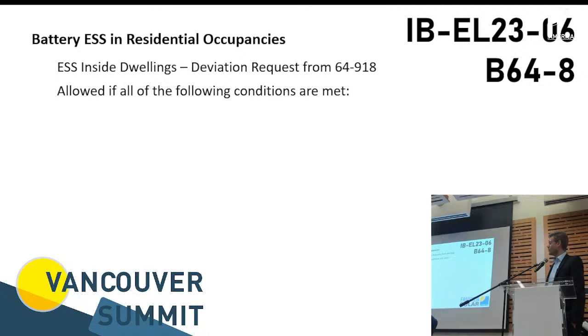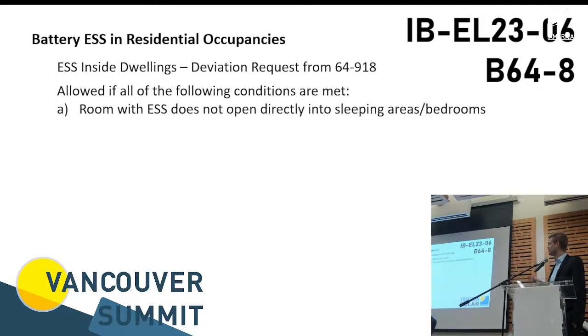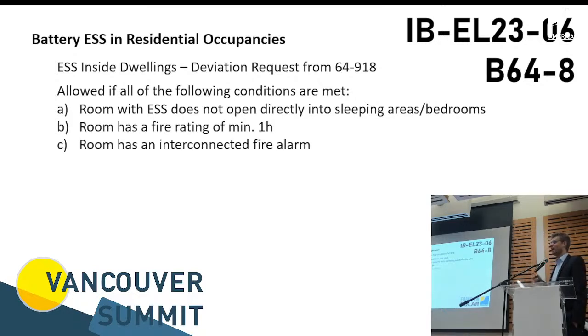When we want to install it in a dwelling, there are certain deviation request options, either in Bulletin 64.8 or under the Technical Safety BC Bulletin IB-EL23-06. If the room where you install the ESS does not open directly into a sleeping area, then you can install it in a utility room, for example, or even a basement. The room has a fire rating of minimum 1 hour, so typically that's double plywood, drywall, and you have to have an interconnected fire alarm system with fire alarms on different levels of the building or different rooms, so that if something happens to that room where the system is placed, the other fire alarms also go off.